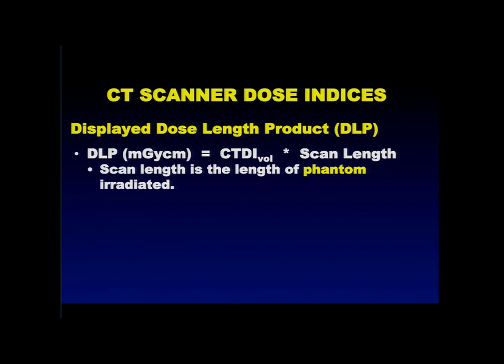Now, DLP, however, is DLP a dose to the patient? No, it's dose to a phantom, because CTDI vol is dose to a phantom. CTDI vol has nothing to do with patient dose, absolutely nothing. And so neither does DLP.